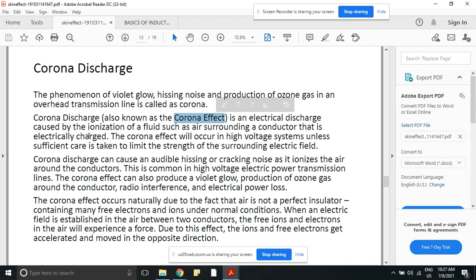It is an electrical discharge caused by ionization of a fluid such as the surrounding air. Because the air around these overhead transmission lines actually works as an insulator. But at higher voltages, it will have the dielectric strength break down, and the air will now become like a conductor and allow the leakage of current to flow. That leakage of current is nothing but what is called the corona effect.